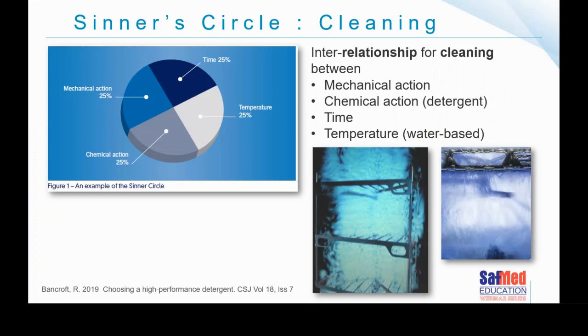When it comes to cleaning, there are four important things that need to happen — an interrelationship between four factors that will produce effective cleaning if they're all in the right balance. We require chemical action — a detergent that has effect on the bioburden we're trying to clean. We need some form of mechanical action — the rubbing and scrubbing required. Then the time, the contact time a device has with the detergent-water combination, and the temperature at which the water and detergent mix. If you have the wrong temperature, it can have a disastrous effect on cleaning efficacy and outcomes.